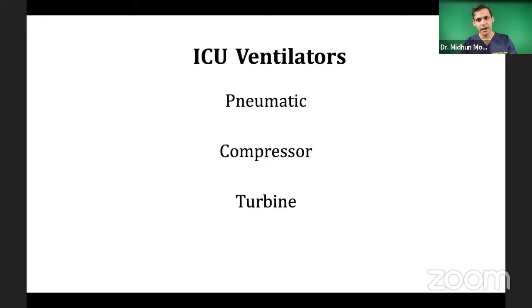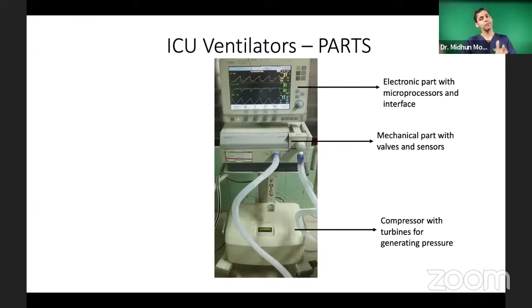Now, ICU ventilators can basically be divided into pneumatic ventilators, compressor ventilators, and turbine ventilators. I'm not going to go into the details of that. You can find all those things in the app. I will be showing all these kinds of ventilators in the Residency app. Just remember these parts of the ICU ventilator. It has an electronic part, which is sort of like the computer, which has all the software, which controls the hardware part. The hardware part mainly contains a lot of valves, sensors, and resistors, which help to measure all the flows and all the pressures. There are flow sensors and pressure sensors, which help to measure the flow as well as the pressure. The volume is calculated by measuring the flow. All right.